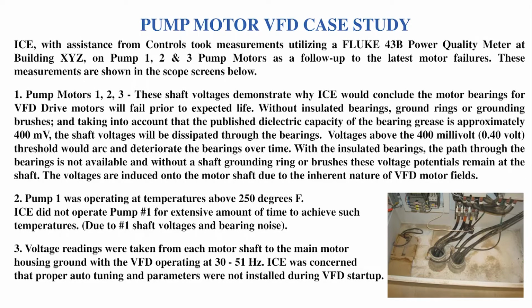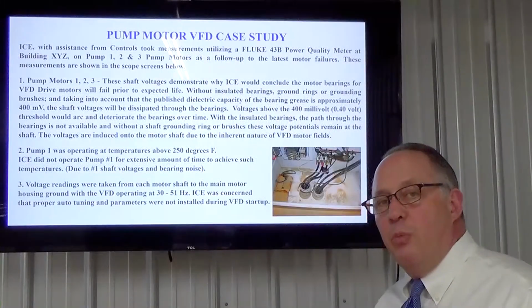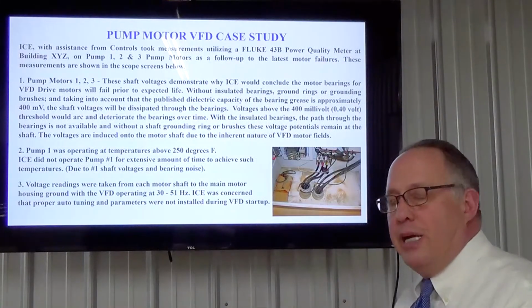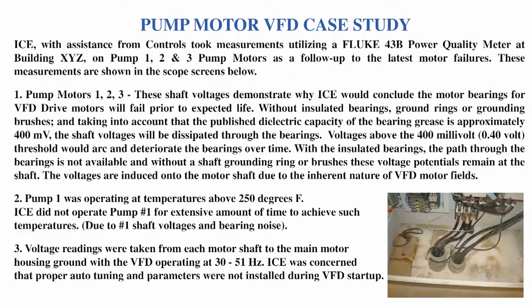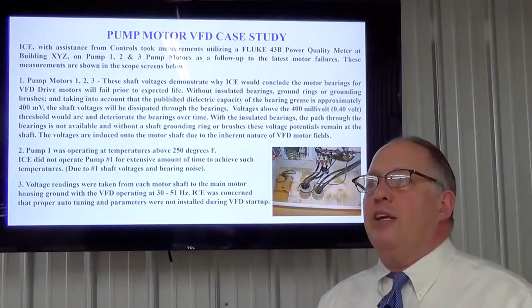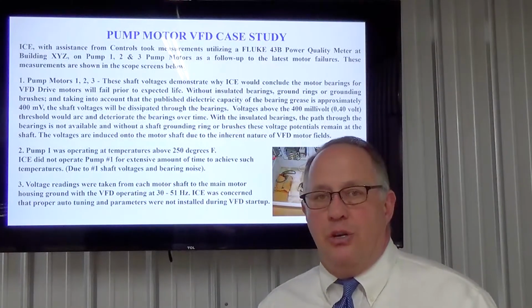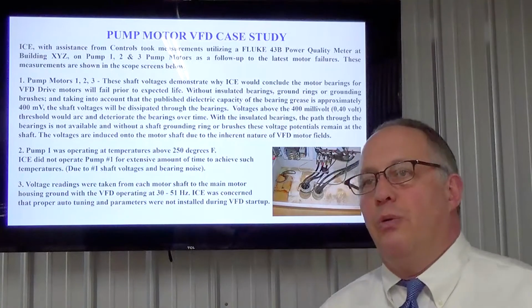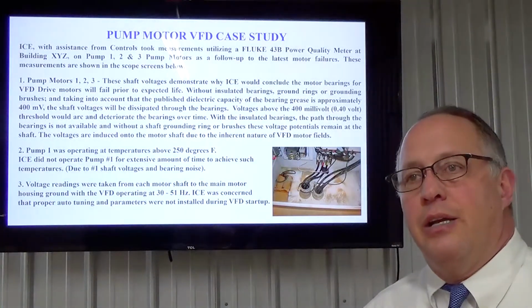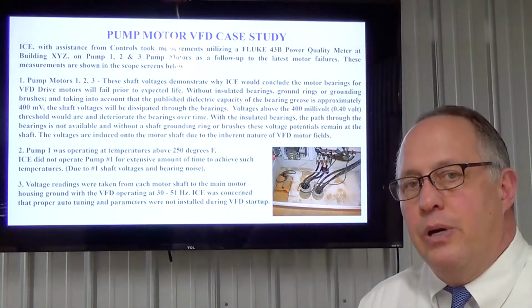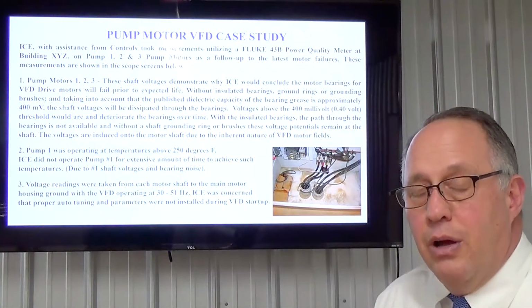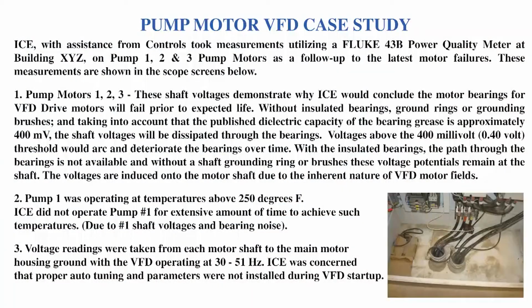ICE, with the assistance from the controls group, took measurements using a Fluke power quality meter, in other words, capable of oscilloscope type characteristics, on pump motors. Now these pump motors themselves were at a large pumping station for a university. In these particular cases, we were looking at 250, 500, and 700 horsepower motors, large motors in this case. As follow-up for motor failures, these measurements were taken. Pumps 1, 2, and 3.